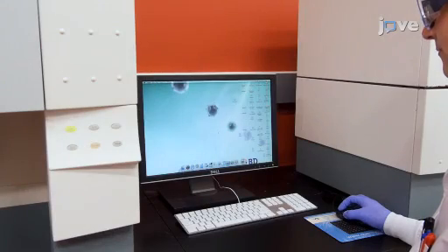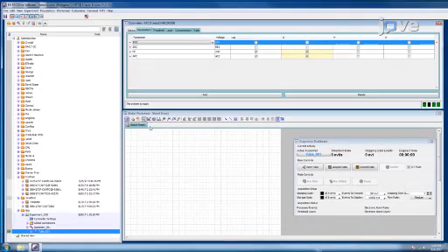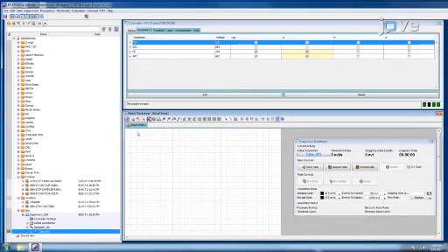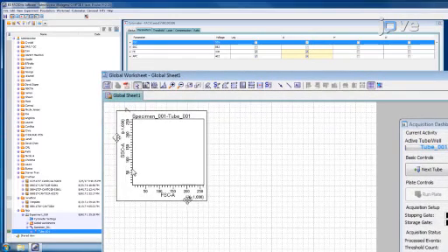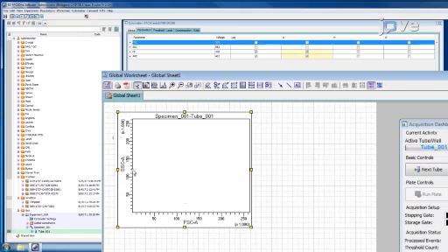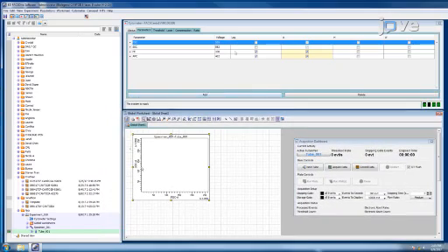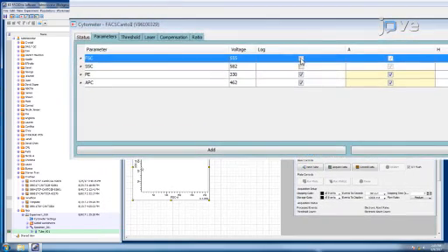Start up the flow cytometer and acquisition software according to the manufacturer's instructions provided with the instrument. Create a dot plot with forward scatter on the X axis and side scatter for the Y axis. Set forward scatter and side scatter to linear mode.